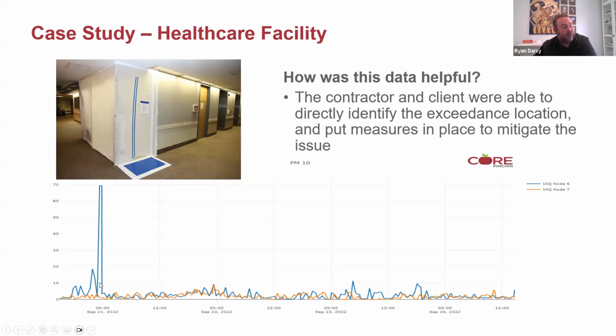To demonstrate this was an effective approach, this graph shows the general indoor air quality conditions in the building over the course of the construction project. You can see there was a fairly high exceedance of dust escaping from the work area. Compared to the other data, which was all well under 10 micrograms per meter cubed, this event spiked to closer to 100 micrograms per meter cubed over that period, showing something was going on within the building related to that construction activity causing particulates to escape the work area.